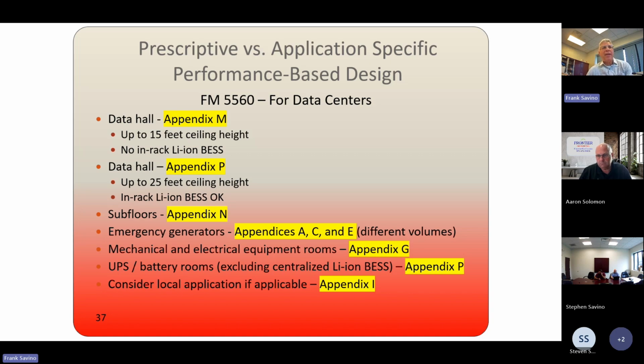It might be that within that requirement, and I believe that there is, you should probably refer to Appendix P, there are going to be requirements for spacing. If you have lithium-ion batteries in racks, spacing between racks are probably going to be a requirement. We could look into that. But well, there's the 9540A testing that allows you to put them next to each other, right? As long as you're below the 600 kilowatt hours in a room, you're meeting the requirement, and you can put them next to each other. So it's just something that you need to get into.